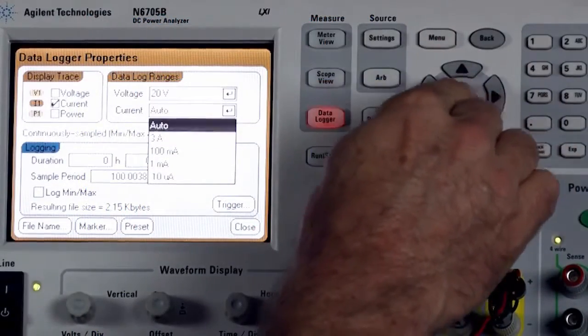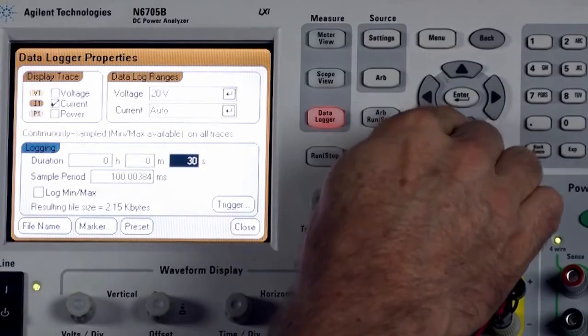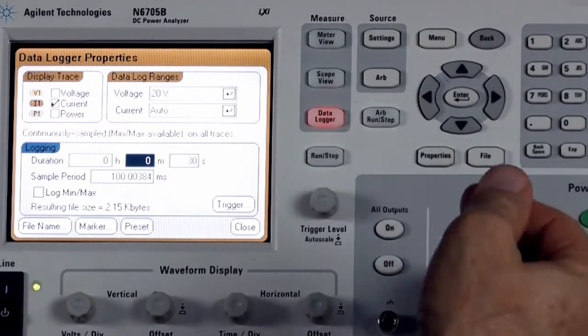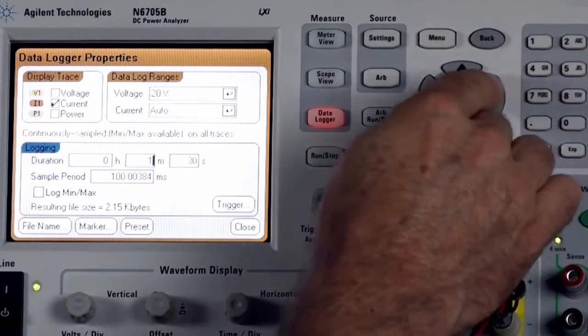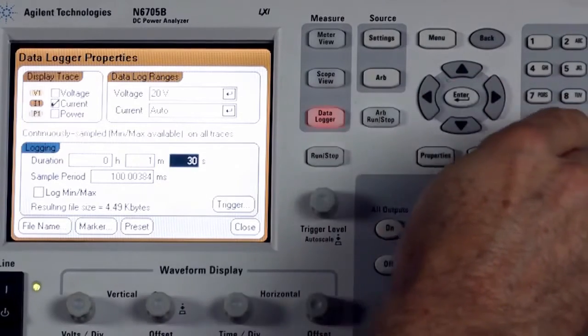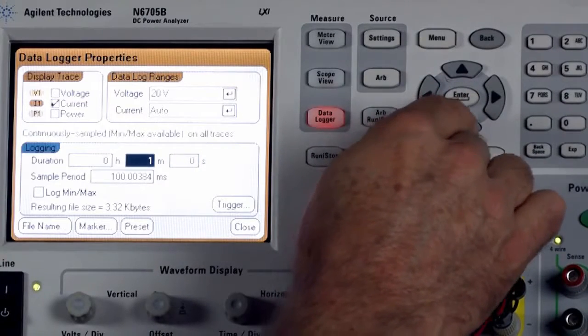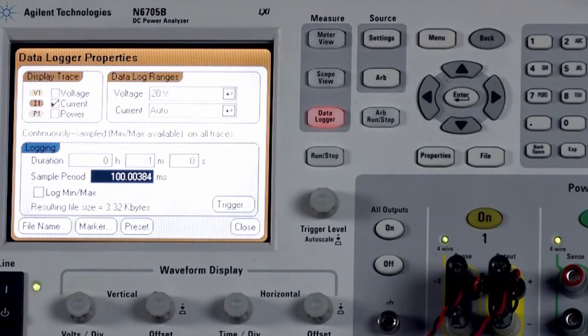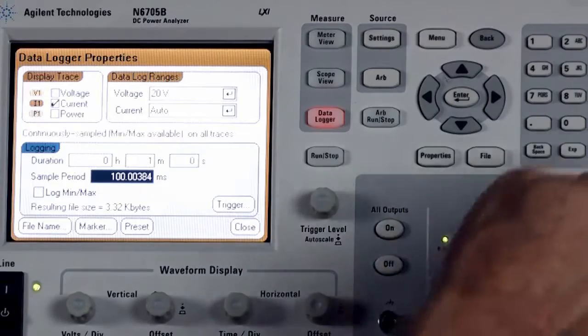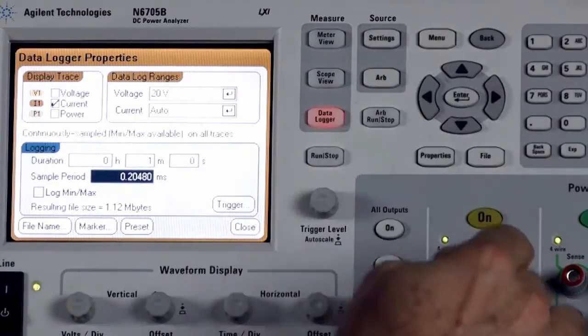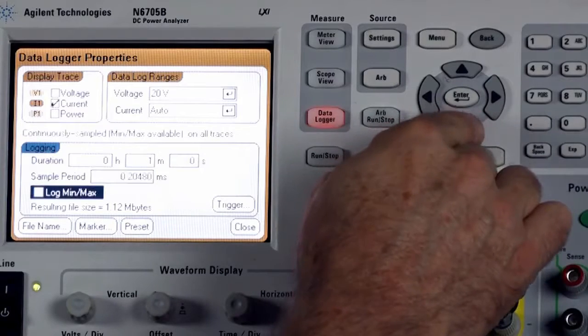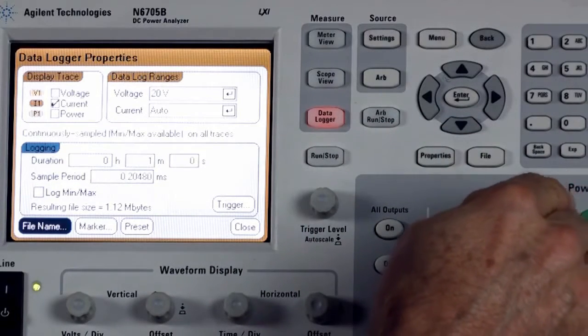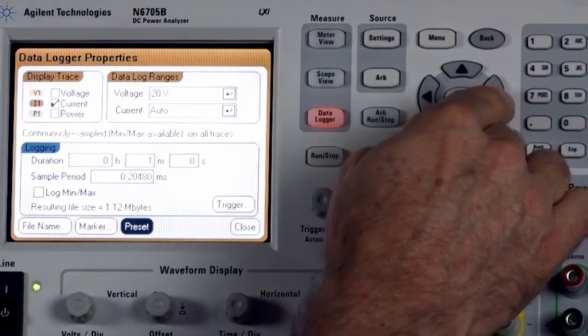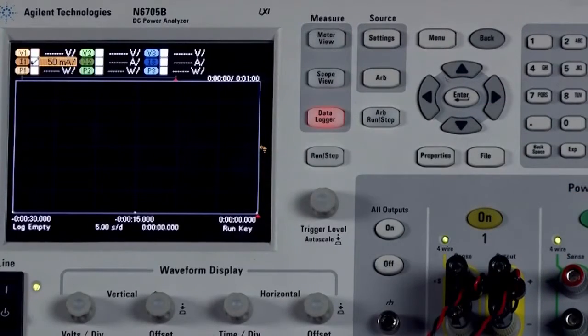So we'll select auto, and then we need to go down and further decide how long we want to log data. I'm just going to choose 1 minute. And then come down to our sample period, and instead of doing it every 100 milliseconds, I'd like a faster sampling, so I'm going to put in 0.2 milliseconds. Okay, so it looks like our resulting file size that will be stored inside our DC power analyzer will be about 1 megabyte. So we save that, and now we move on to step 4.